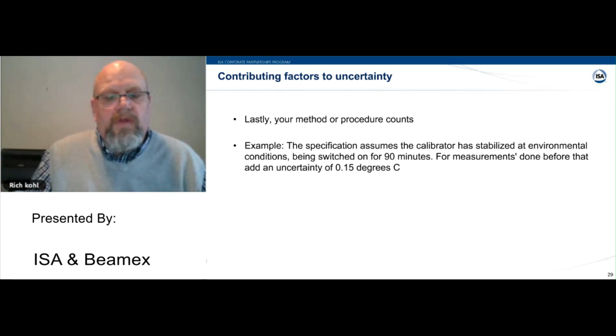So if your M&TE, your test equipment manual, makes a statement like this, you can't just go from the trunk of a cold or hot car, say, walk into the factory floor and take your measurements right away. You need to wait for the test equipment to come to thermal equilibrium with the environment it's being used in. This is actually a thing that we got burned on early in our attempts to get 17025 accredited for field calibrations, because we had guys doing exactly that. They weren't waiting for it, and so it was a write-up, and we had to change our processes and procedures to make up for that.